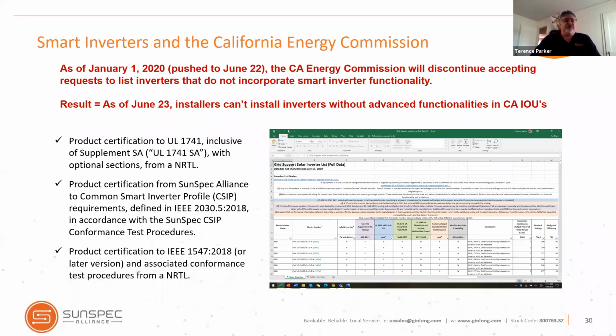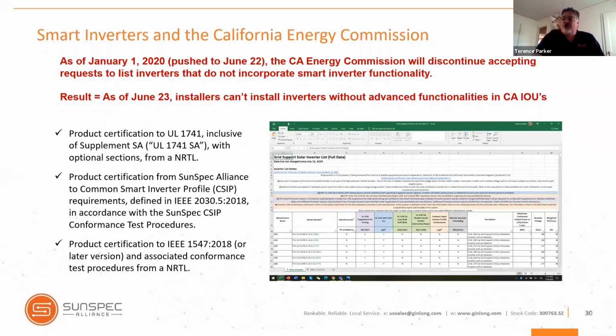They have to make sure their products are certified to UL 1741 SA. They need certification to the CSIP requirements defined in 2030.5-2018. And they need their product certified to 1547 or later versions for conformance to test procedures from a NRTL. That's really what installers need to do.